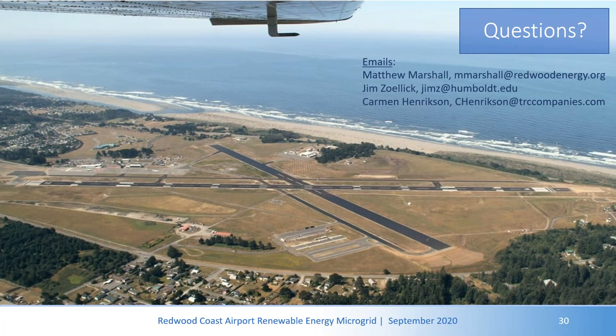So we're headed toward better visibility and better control where needed. But their control of the system—when grid connected, they're not controlling anything, unless there's a safety issue or things are way out of whack, in which case we have protection relays that would disconnect the generator. That's the case for any interconnection with any DER. And if we're in islanded mode, the generation has to meet the load, and it has to meet it exactly. So something might be curtailed if necessary, but again, that's just for safety and quality reasons.